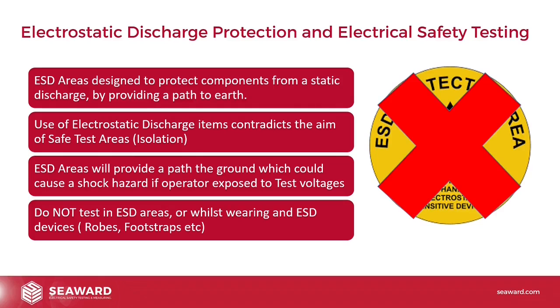ESD areas provide a path to ground and could create a shock hazard if the operator is exposed to the test voltages. So do not test in ESD areas, and also while wearing ESD devices. So they could be the robes, the foot straps, the little wrist bracelets that you plug into a socket or clip to a radiator, those kind of things. We don't want any of that. We want to keep you isolated.